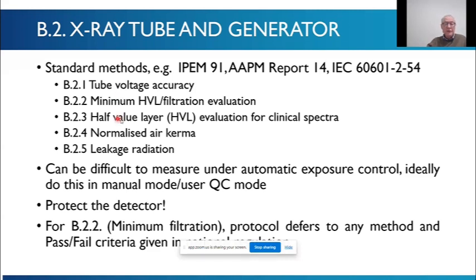And then half value layer for the clinical spectra. So this is kind of an acceptance test, or at a new tube, for example. And then dynamic imaging systems often have filtration that changes greatly depending on what's in the beam load. If you're imaging a certain protocol and you have quite a thin patient thickness, you might have quite a lot of spectral filtration, or copper or tantalum filtration, for example. And if you go to thick, large patient thicknesses, that will be gradually removed.